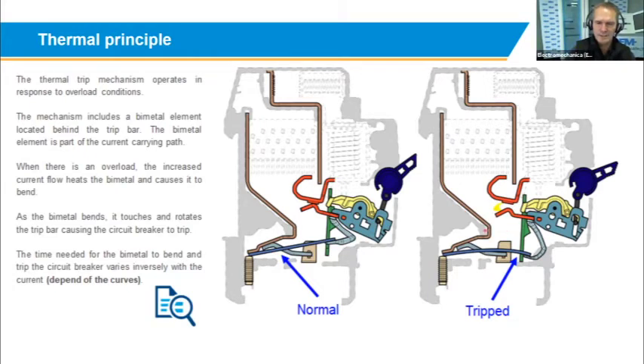And this is where the derating of the product that I mentioned comes in. These products are calibrated at 50 degrees C. So even if the temperature inside the distribution board is 50 degrees C, the bimetal will stay in the same position and will not trip. When we get to the tripping curves, you also see that a circuit breaker rated at 100 amps will be able to carry 100 amps and actually never reaches the tripping curve, and it will carry on forever and a day, and it will never trip.